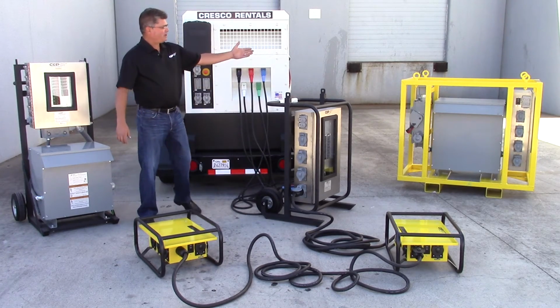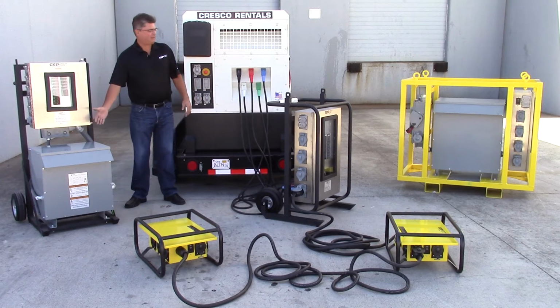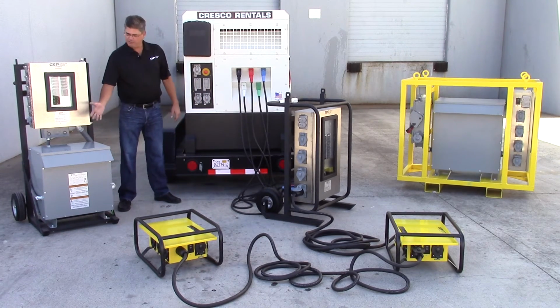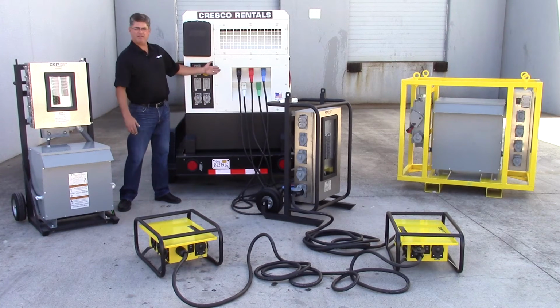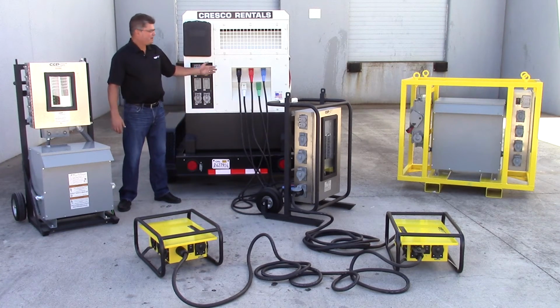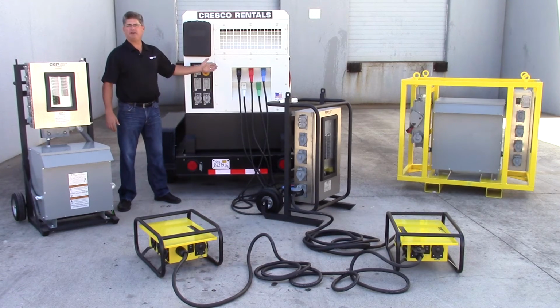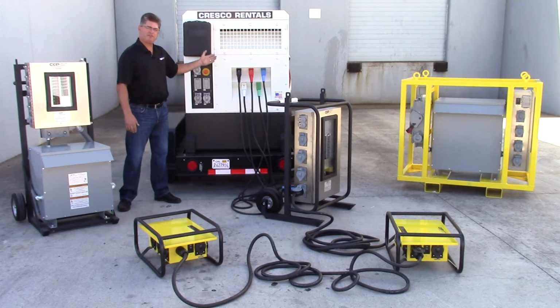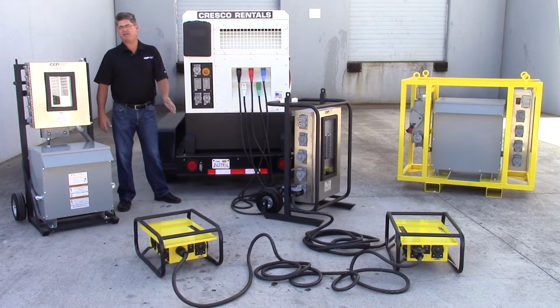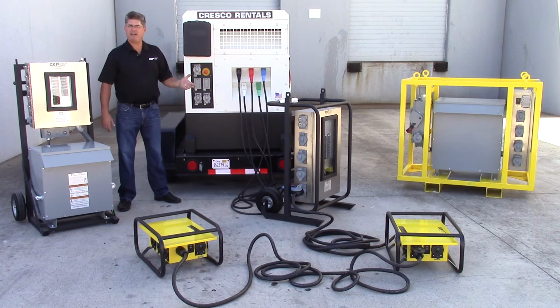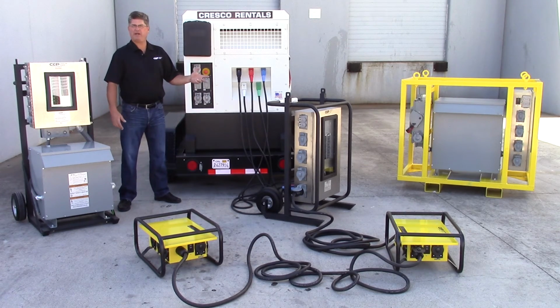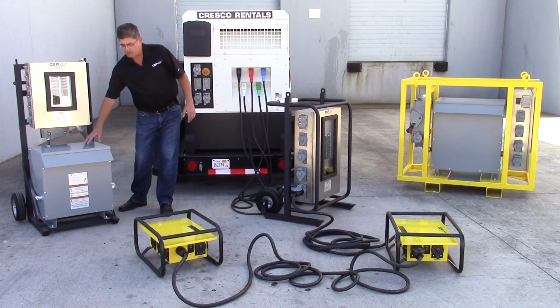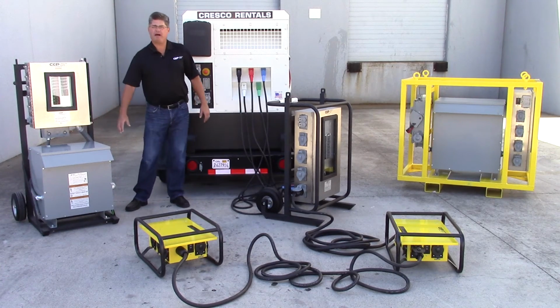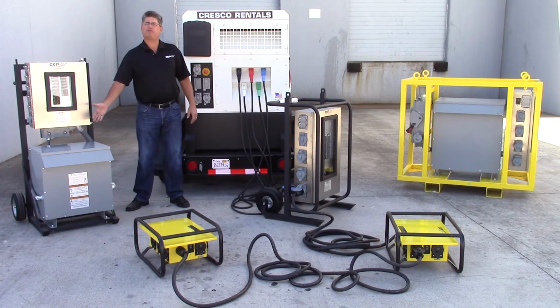Moving on, we have some larger units here that utilize step-down transformers. Now where these would be utilized is if you had to move your power source a long distance from where the generator or your power source is. With this, we would use smaller cabling with higher voltages to distribute and carry that power the longer distance. This leads to less line loss and therefore greater efficiency on your power. With that though, we're carrying 480 volts out to your power source, which requires the use of a step-down transformer.